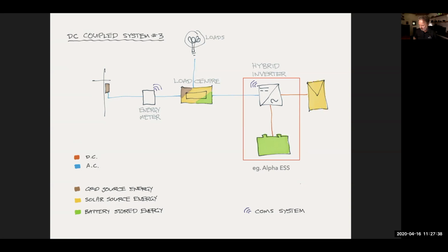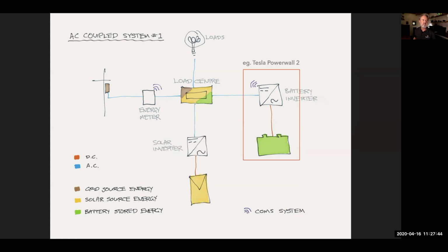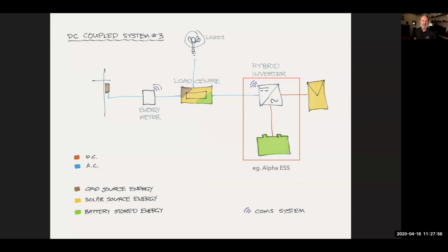So let me just contrast the AC coupled. I'll take you back to that slide just to remind you. That's AC coupling, right? We're connecting via the AC network a battery inverter system to a solar inverter system, and it's an easy retrofit solution, whereas this is a DC coupled solution. This would be more typical of a new build where you want everything in the one package. You want the inverter to have batteries connected to it and a PV array. There are some advantages in doing this, but just as with the AC coupled system, it's important that the energy meter is upstream of all the loads. Otherwise, it can't see when to support those loads.